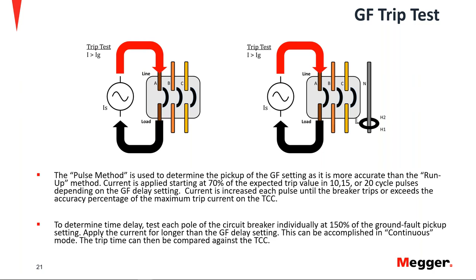Once we have the pickup, we can determine the time delay for each pole, starting at 150% of the pickup value. You do a continuous injection, configure your instrument to inject for longer than the delay setting to ensure coverage. Once you have your recording, you compare against the time current curve for that breaker.